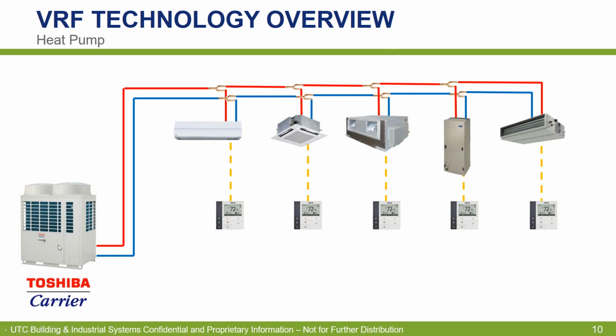It's another diagram here, outdoor unit. Heat pump, obviously, right? We're not seeing any flow selector boxes. That's the number one takeaway: if you guys are ever looking at plans and you don't see any intermediate boxes in between the outdoor unit and the indoor units, that's telltale that it's going to be a heat pump system.